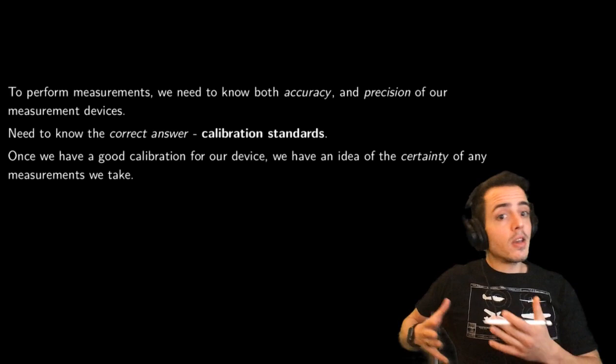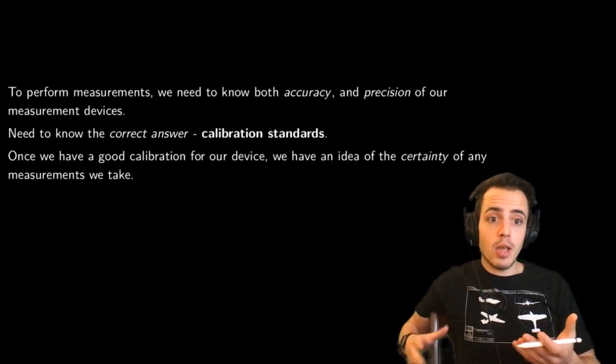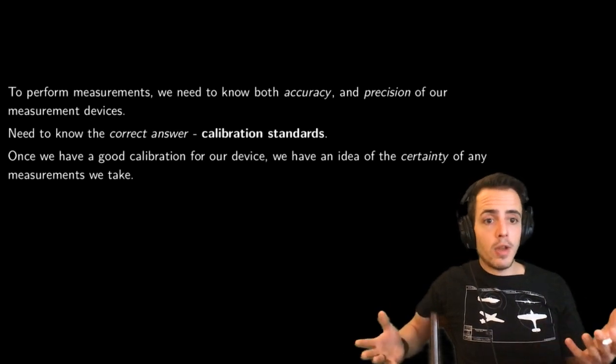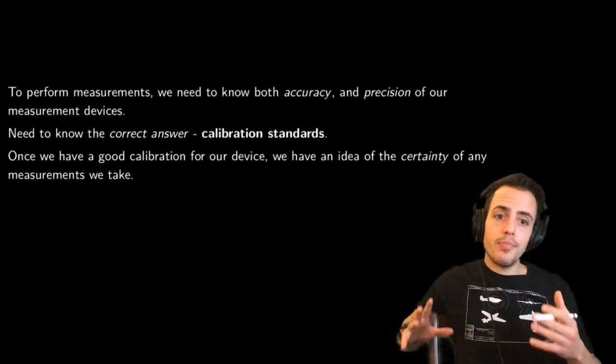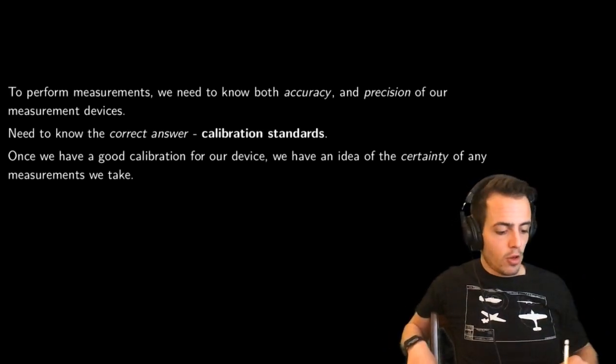Very similarly, with transducer calibrations, we've got an idea about how much they might fluctuate within a certain measurement period or for a certain measurement amount, and we then know that we shouldn't trust any fluctuations below those bounds.